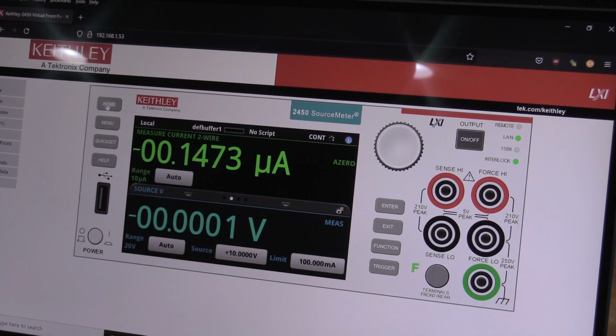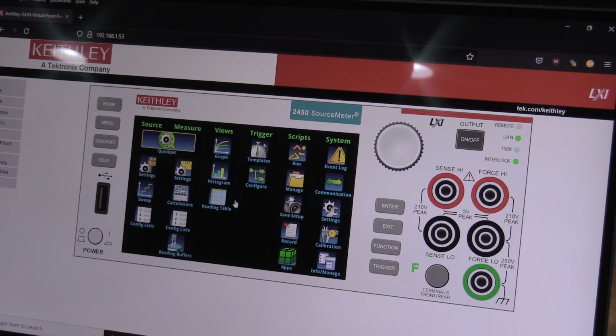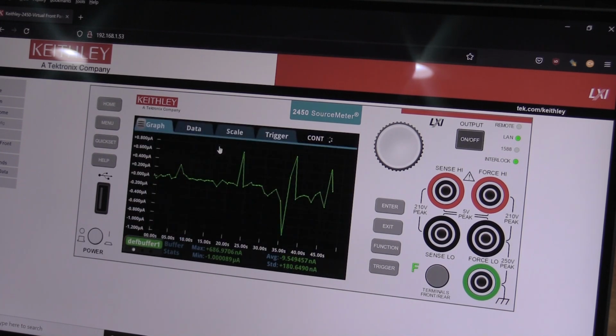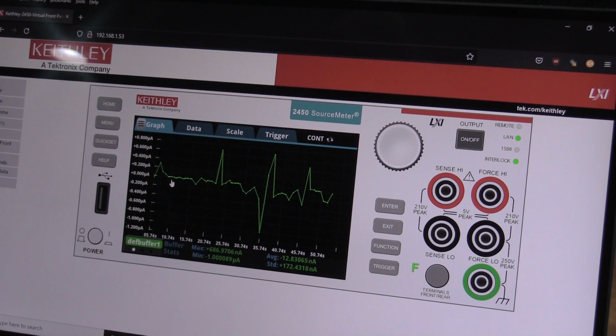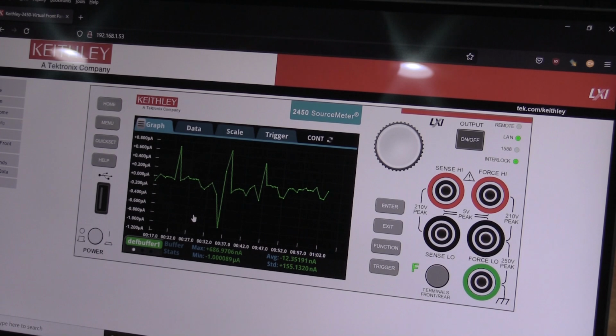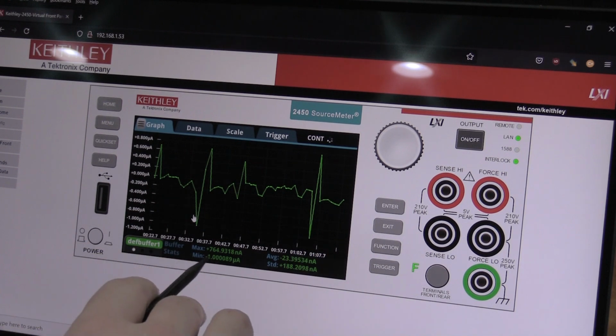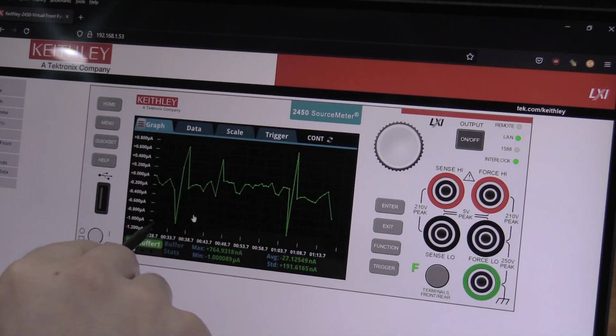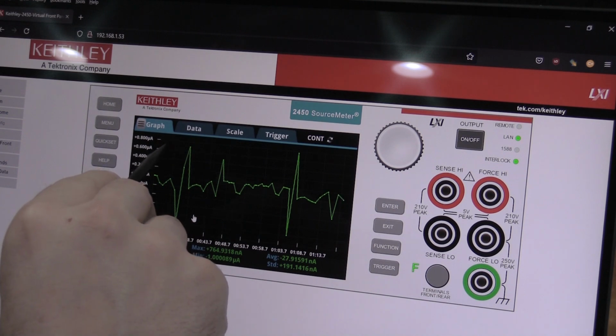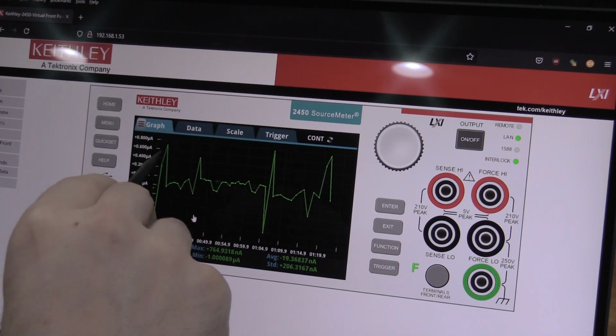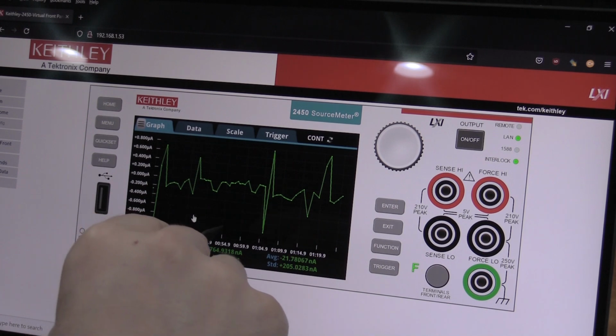So what I'm going to do is go to graphing mode. Now we have current on the vertical and time on the horizontal. So what I'm going to do is clear the buffer, and then trigger the output. What we're going to see is a spike to 100 milliamps, and then as the capacitor reforms, we'll see a slow drop off of the current going through the capacitor till it hits a very low level.